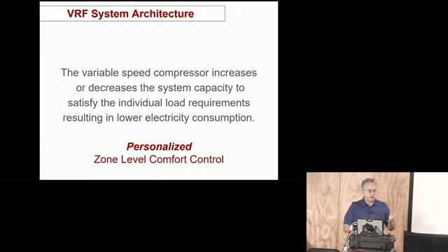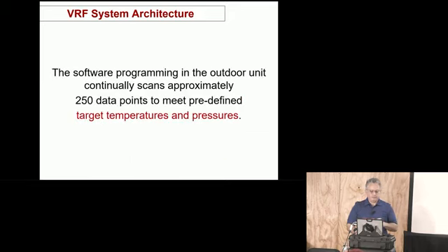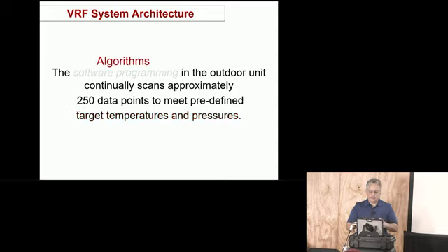One manufacturer coined this term, personalized comfort. So personalized zone level comfort control. That's how we can look at each indoor unit. The software programming in the outdoor unit continually scans approximately 250 data points to meet predefined target temperatures and pressures. Okay, these are already written, and instead of saying software program, we could say algorithms.